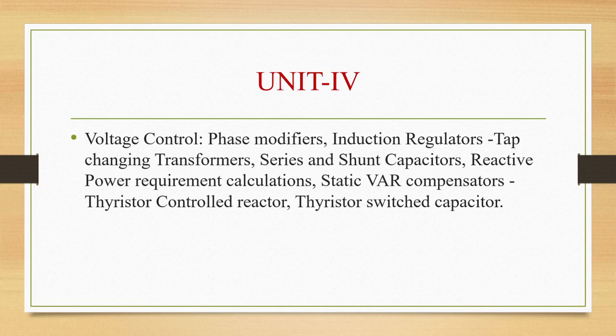Now if there are variations in the voltage, then it can cause some erratic operation or malfunctioning of consumers' appliances. So to safeguard the interest of the consumers, government has enacted a law in this regard. So the statutory limit of voltage variations will be plus or minus 6% of declared voltage at consumers terminals. Okay, so the voltage can be plus 6% or minus 6%, and that is okay at the consumers level, and the appliances of the consumers will be functioning properly.